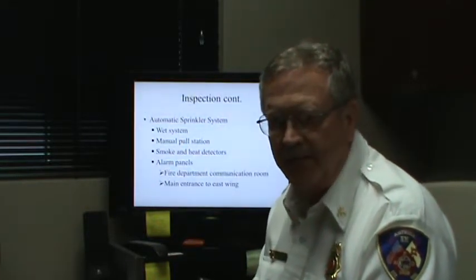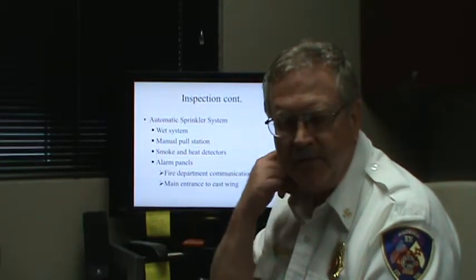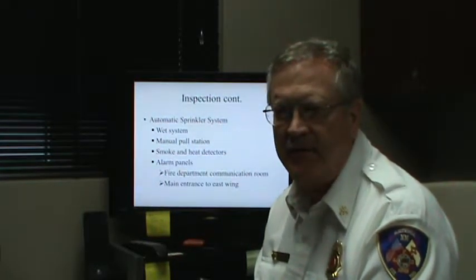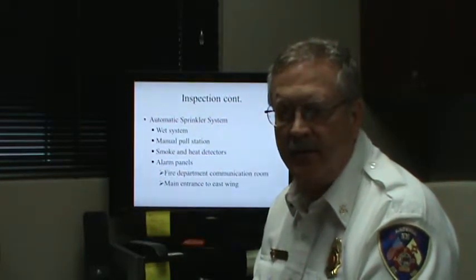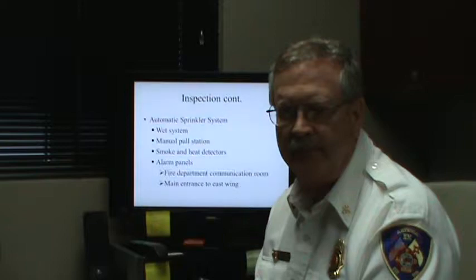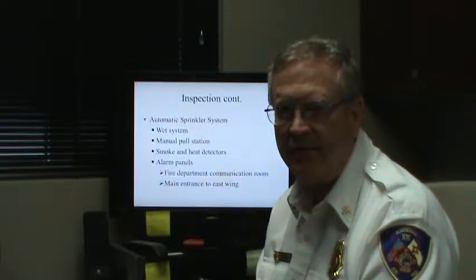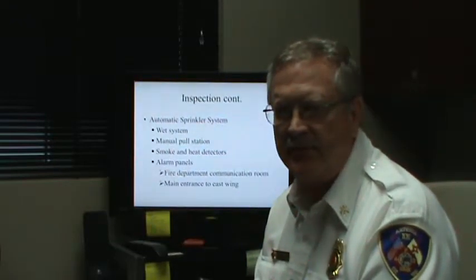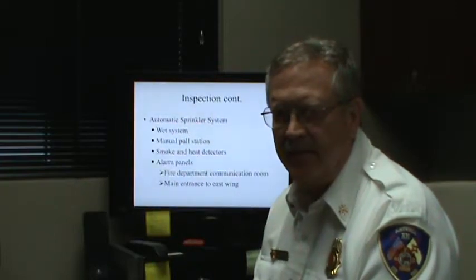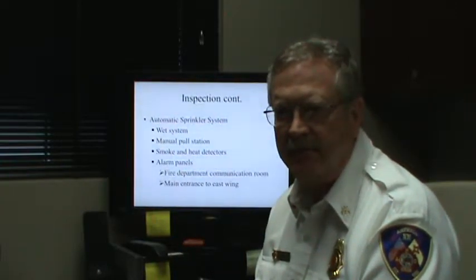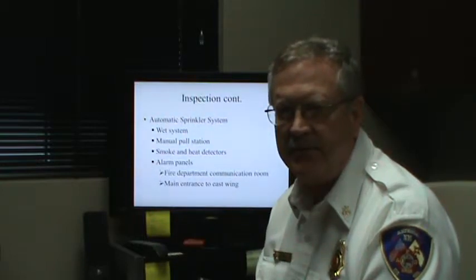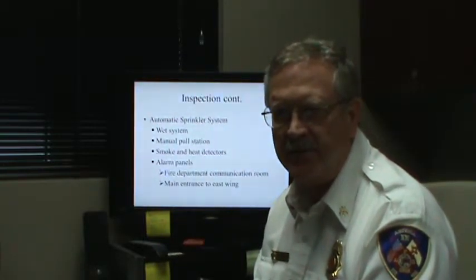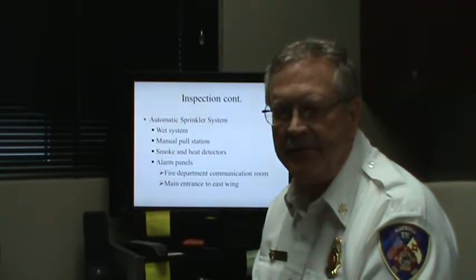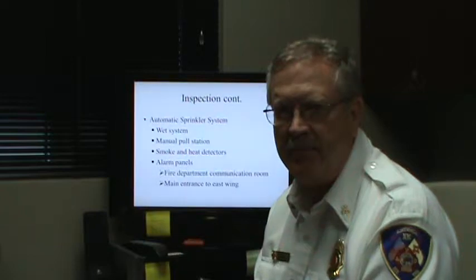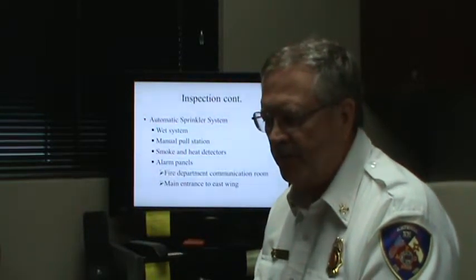Now, when I did the inspection, I notified our central dispatch and let them know that I would be testing, so that if they did receive an alarm from the alarm company, not to be concerned about it. They could call me and say there was an activated alarm, which was accomplished. So when I pulled the pull station, the strobes went off, the alarms functioned as they were supposed to, and then the monitoring company called our central dispatch, and the central dispatch contacted me to let me know that alarm had been activated.